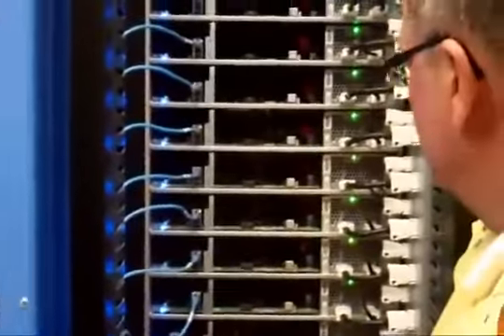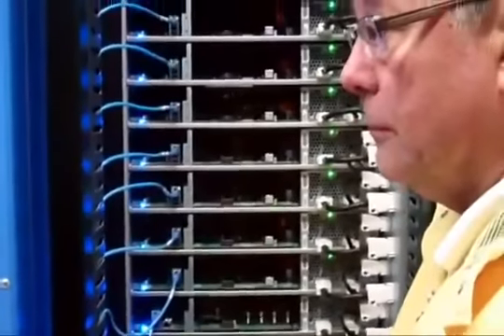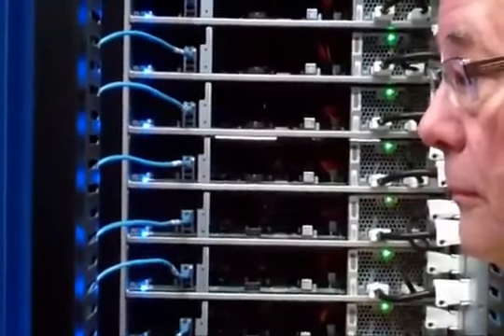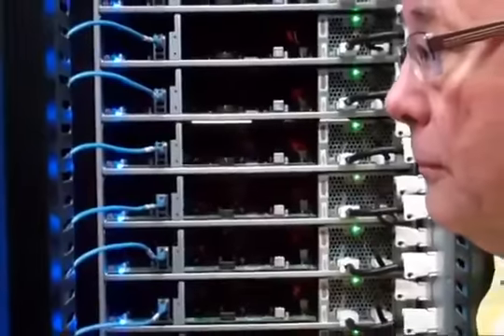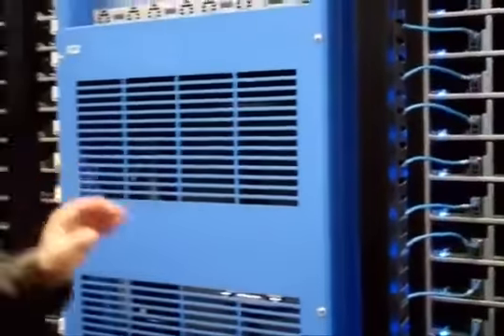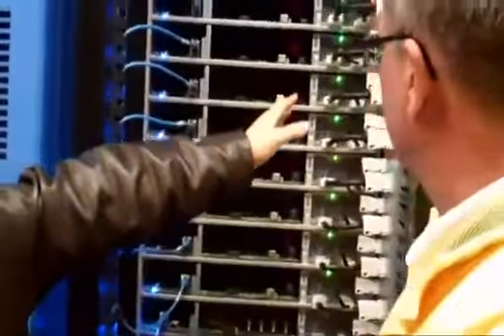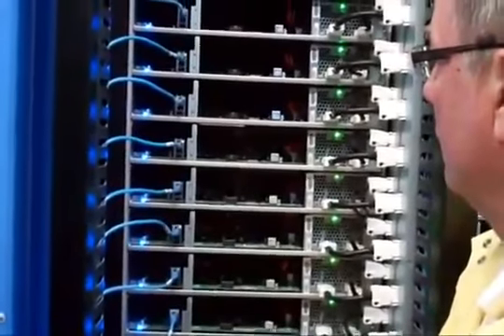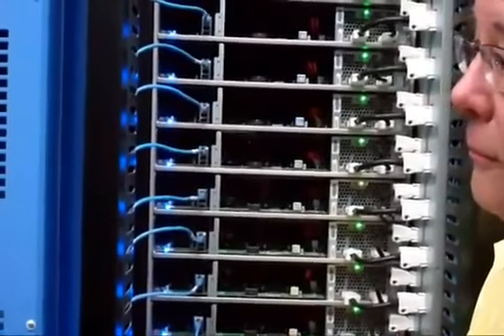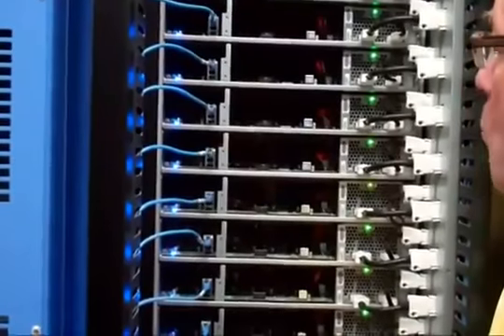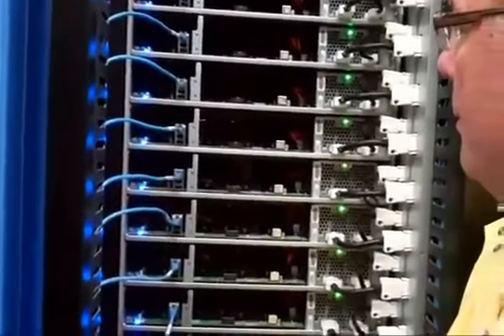The DC power strip is only used in case we lose utility power, then the DC power gets supplied into the data center. This power supply is actually running at 277 volt AC, and it has about a 94.5 percent efficiency. It's very high. Everything is accessible from the front. So the power cables, the network cable, and once you disconnect these cables, all the tray just comes out without using any tools.